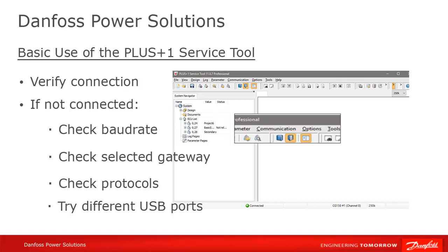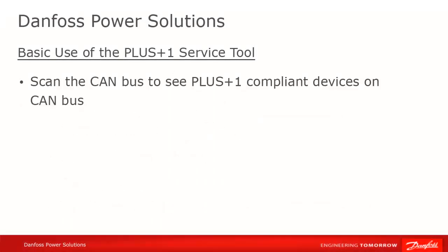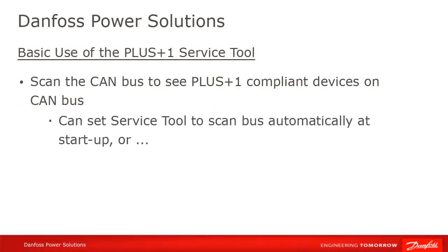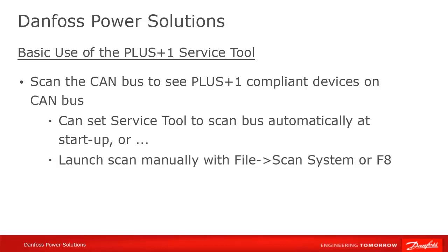You might also want to try different ports on your desktop or laptop, and try to avoid using a docking station port. Once you're connected, the system should immediately scan and display a list of any Plus One devices that it finds on the CAN bus at startup. You can also initiate a scan by pressing F8.